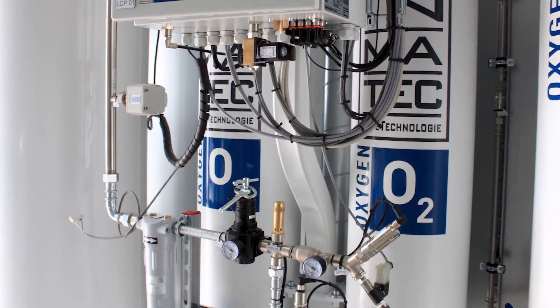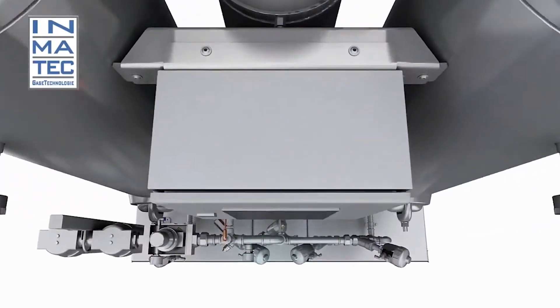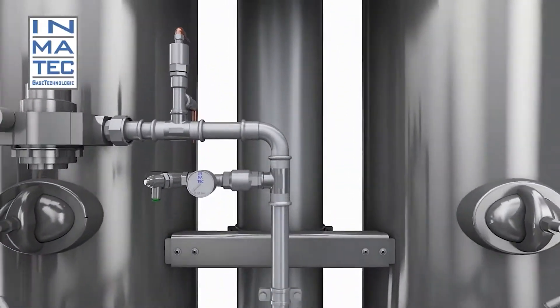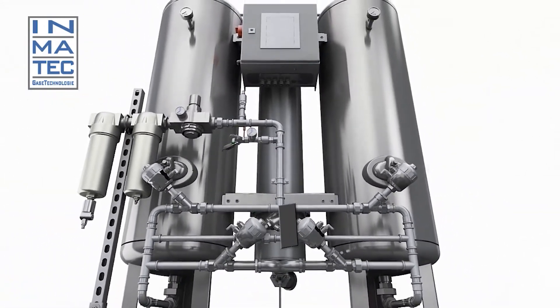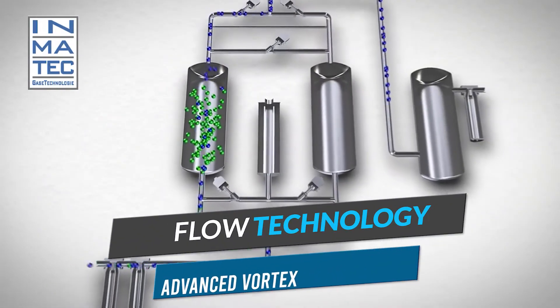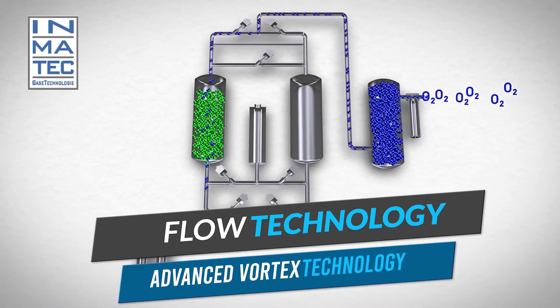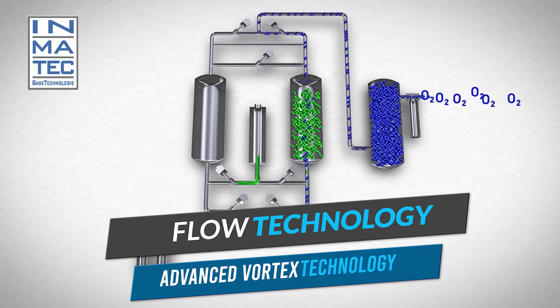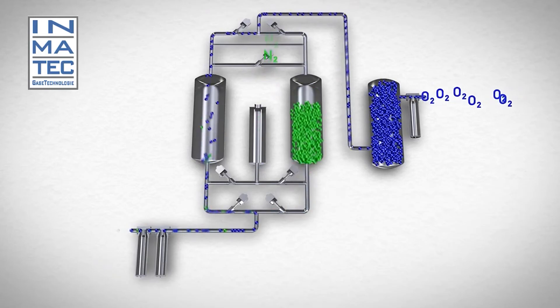The POC medical range uses the new POC technology developed by Inmatec. This increases the efficiency of the PSA technology used to separate oxygen molecules from nitrogen molecules. Thanks to innovative flow technology combined with advanced vortex technology, less compressed air is required, and energy costs can be significantly reduced by extracting more oxygen with lower compressed air requirements.